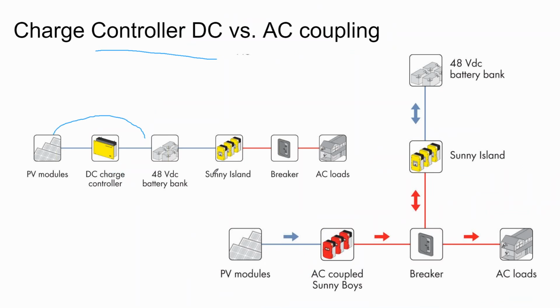Now, on the flip side, where going with the higher voltage, higher amperage, larger battery products comes back to haunt you is that they're just not manufactured in very sufficient quantities. So each of these charge controllers lands on a DC breaker, but when you think about it, this is a 600-volt input, and one circuit of modules is about 8 amps, and lo and behold, this is a 4.8 kilowatt charge controller. It can fit almost one pallet of solar modules on it, not quite. Okay, well now it's coming out on a 48-volt battery bank, and so the breaker is sized for 100 amps.